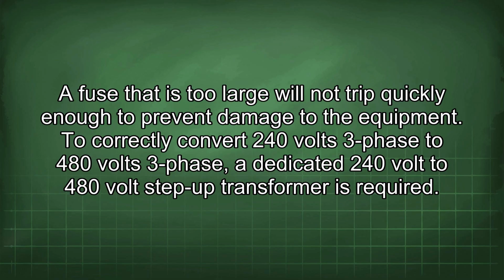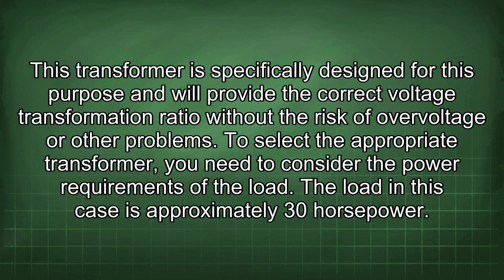To correctly convert 240 volts 3-phase to 480 volts 3-phase, a dedicated 240 volt to 480 volt step-up transformer is required. This transformer is specifically designed for this purpose and will provide the correct voltage transformation ratio without the risk of overvoltage or other problems. To select the appropriate transformer, you need to consider the power requirements of the load. The load in this case is approximately 30 horsepower.